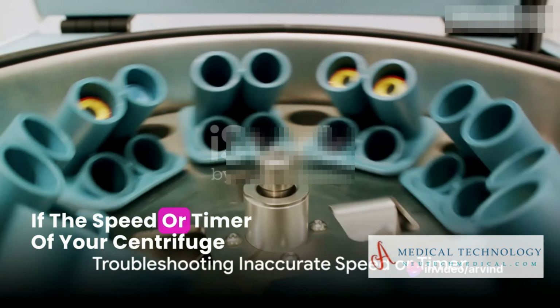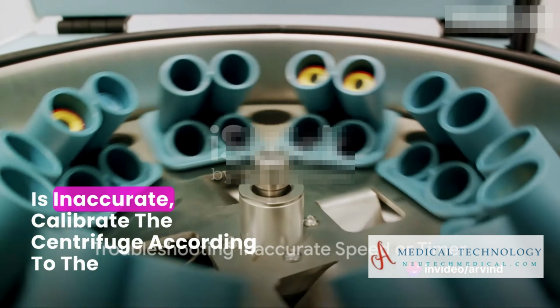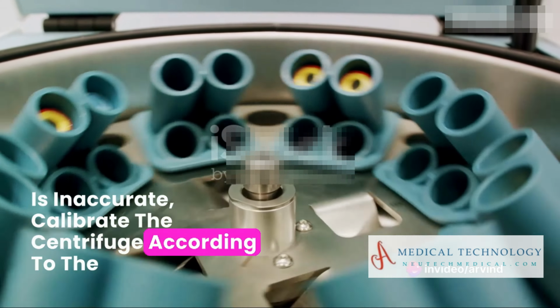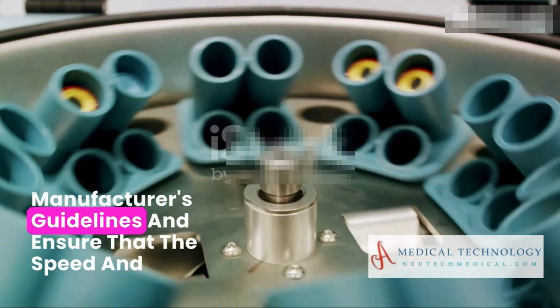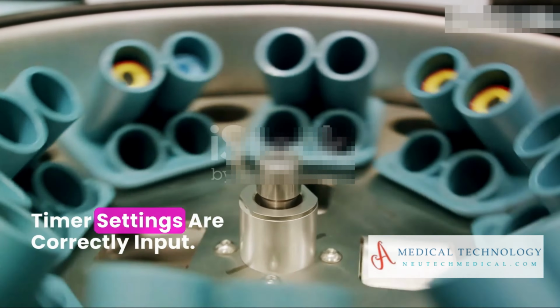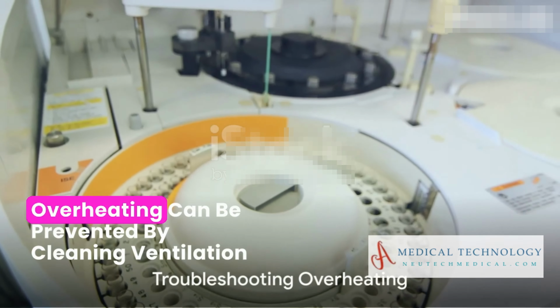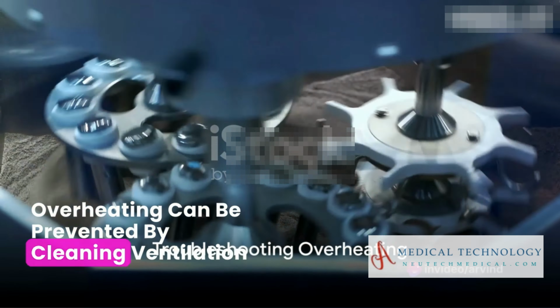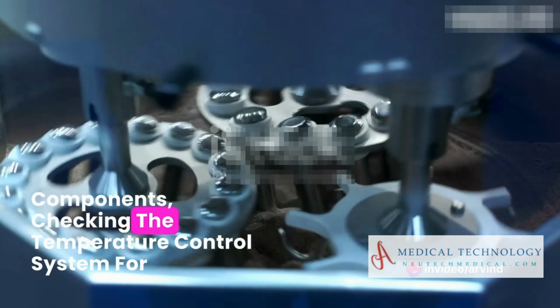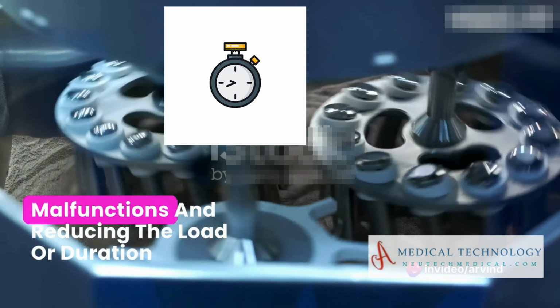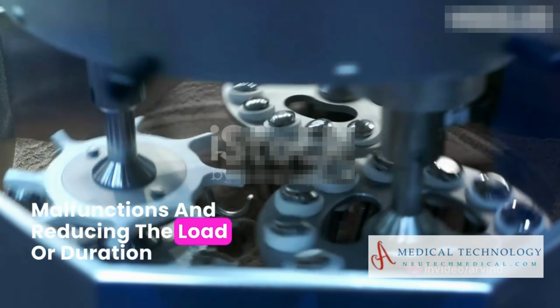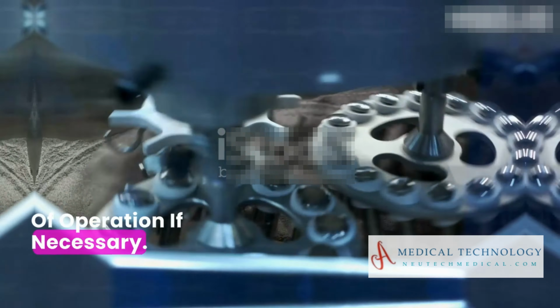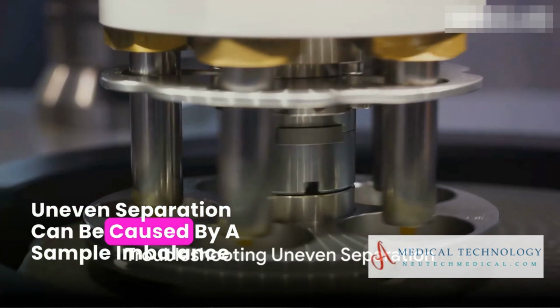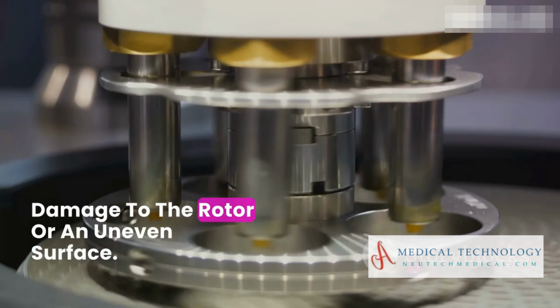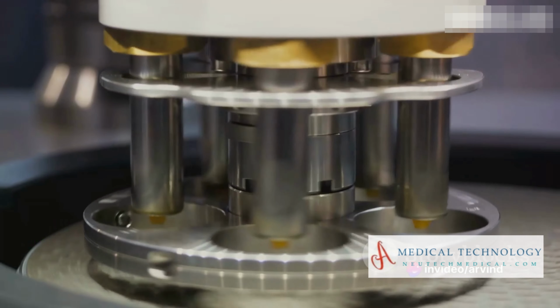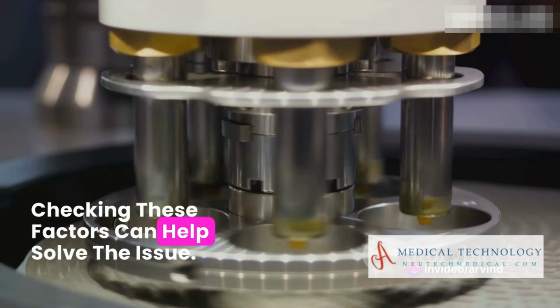If the speed or timer of your centrifuge is inaccurate, calibrate the centrifuge according to the manufacturer's guidelines and ensure that the speed and timer settings are correctly input. Overheating can be prevented by cleaning ventilation components, checking the temperature control system for malfunctions, and reducing the load or duration of operation if necessary. Uneven separation can be caused by a sample imbalance, damage to the rotor, or an uneven surface. Checking these factors can help solve the issue.